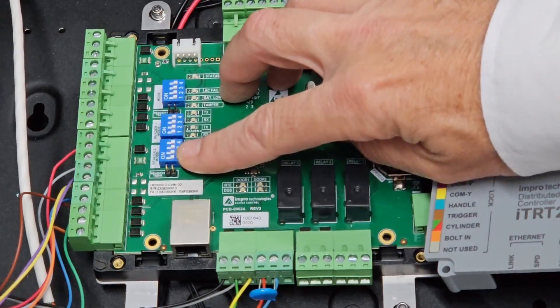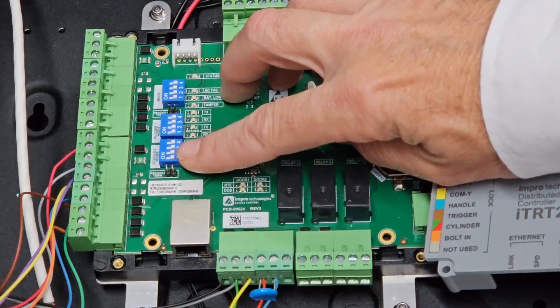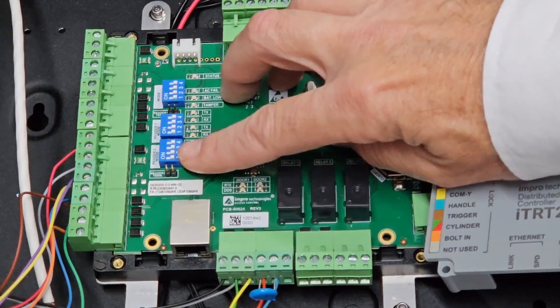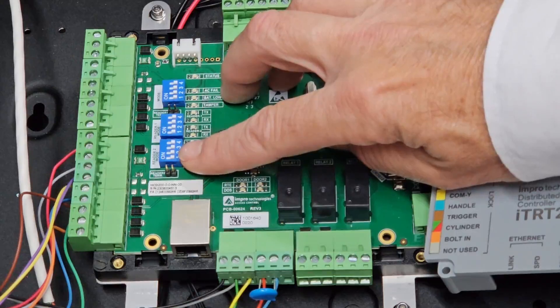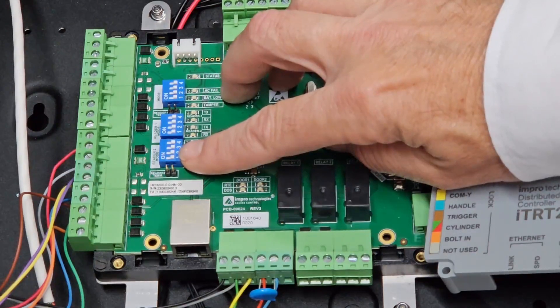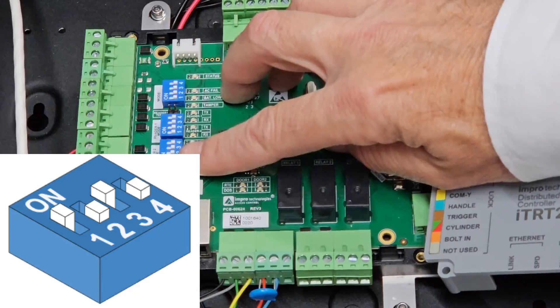These bottom switches, the reader 2 switch, will set up how many OSDP readers will be connected to the reader port. In this installation, we will have both entrance and exit readers, so we need to set this to 1010, that's on-off, on-off.